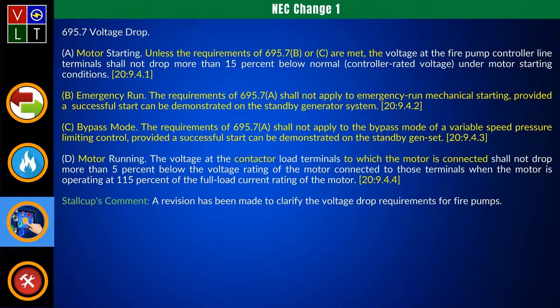Yeah, I'm going to go back and grab, because we did a publication. We didn't sell a ton, but we still have all the information that covers every calculation in the code. And we actually show 695.7(A) and (D) for the 2023 here, how to do those voltage drop calculations at 15%, or if it was a motor running at 5% operating at 115% of the full load current rating of the motor. I think I might do a course one evening and go back, grab this information, show everybody how to do the voltage drop calculations here, and then show the original ones like we did before.